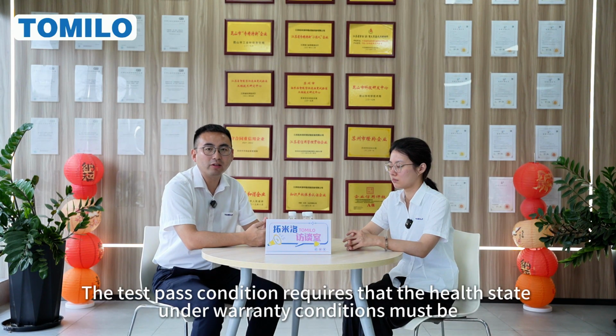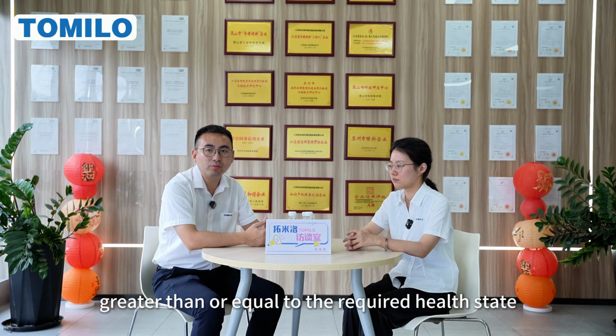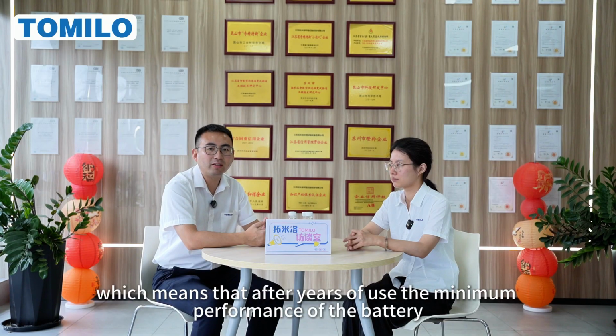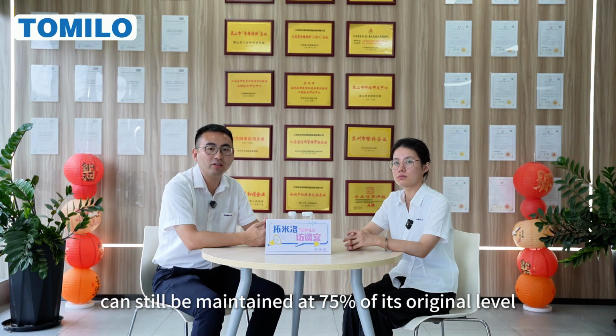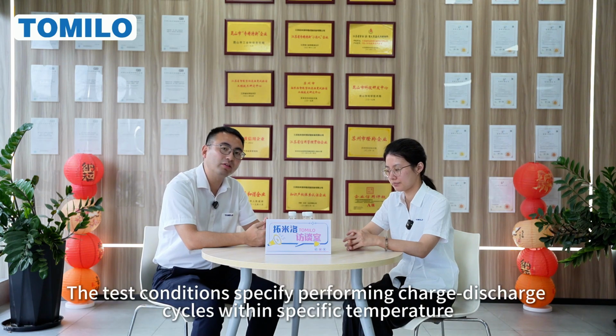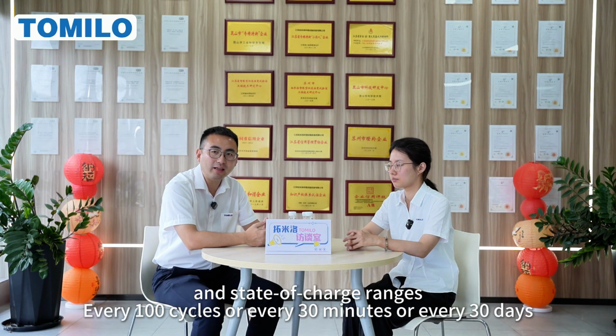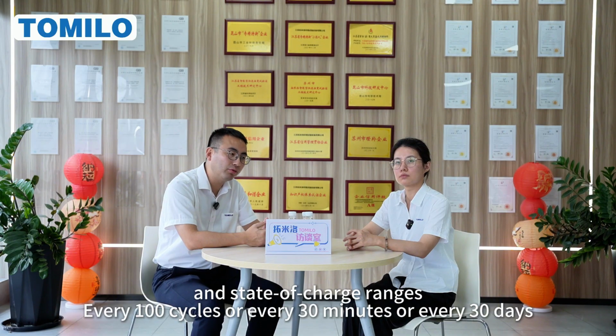The test pass condition requires that the health state under warranty conditions must be greater than or equal to the required health state—meaning that after years of use, the minimum performance of the battery can still be maintained at 75% of its original level. The test conditions specify performing charge-discharge cycles within specific temperature and state of charge ranges every 100 cycles, or every 30 minutes, or every 30 days.